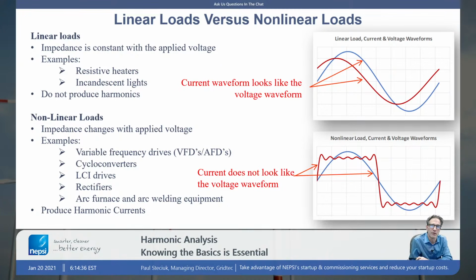So linear loads versus nonlinear loads. The top curve here shows a linear load, and if you put a sinusoidal voltage across a linear load, you'll get a sinusoidal current. In other words, the current matches the voltage. So you apply voltage across a load, you get a current flow through it, they match. One on the bottom, we apply to a nonlinear load, and this might be, say, a power supply to a computer. If we apply a sinusoidal wave to the load of a computer, the actual current wave shape will be a square wave, similar to what you see here.